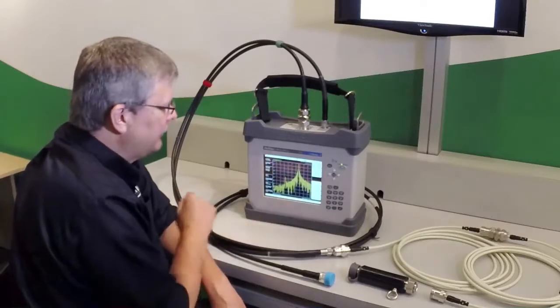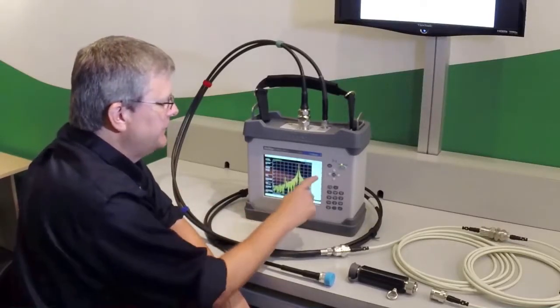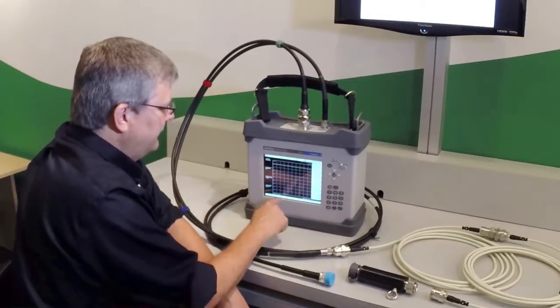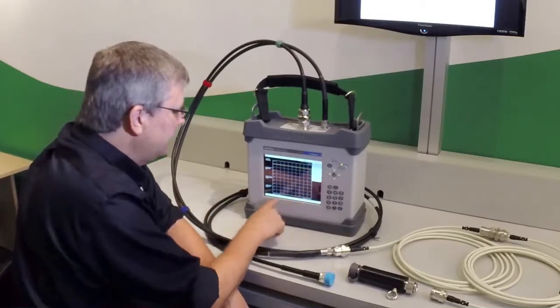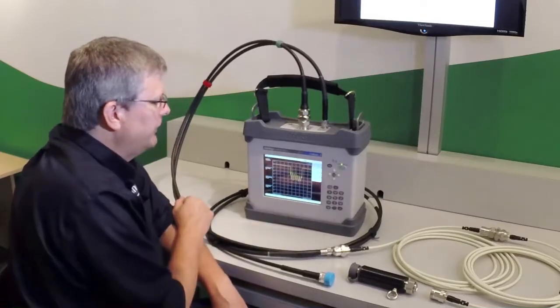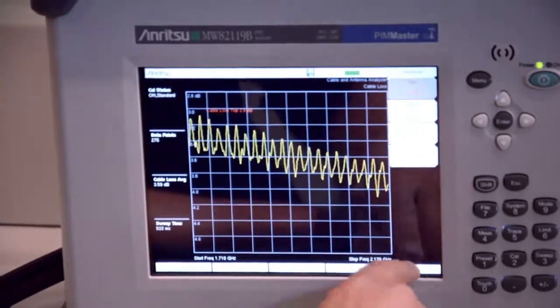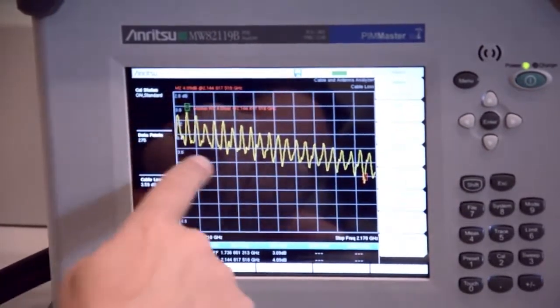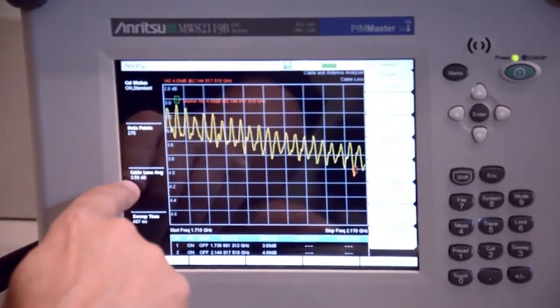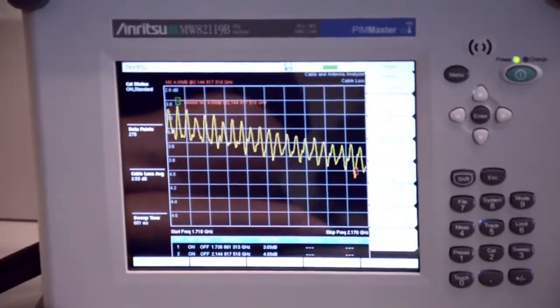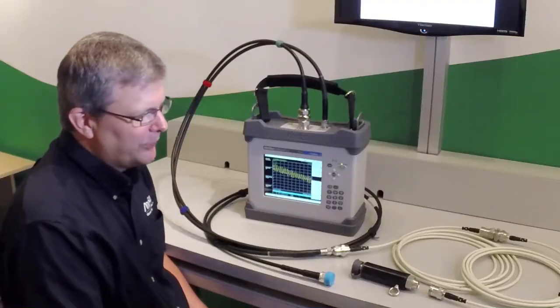While the cable is open, the next logical test to do is go into the measurements menu and perform a cable loss test. I'll do the amplitude to auto scale. In the marker menu, we have an automatic feature to automatically apply markers at the peak in the valley. And so it shows us here that the average cable loss is 3.59, but I've also put markers at the peak and the valley in case someone wants to go and mathematically verify that measurement.